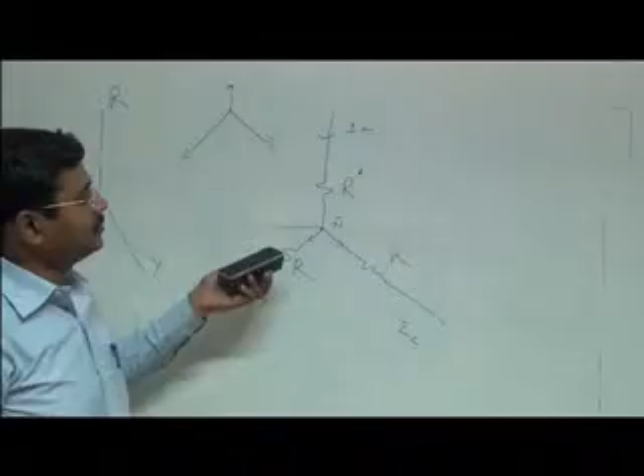Now, what are the ill effects of harmonics? As we have seen, harmonics come at the load end, and because of harmonics, negative sequence and zero sequence currents are generated, and in machine it produces heating, noise, and torque pulsations. In transformer, since harmonics are at higher frequency, and since frequency increases, the copper losses increase, there is an audible noise and heating. For generator, it reduces the thermal capability of generator.